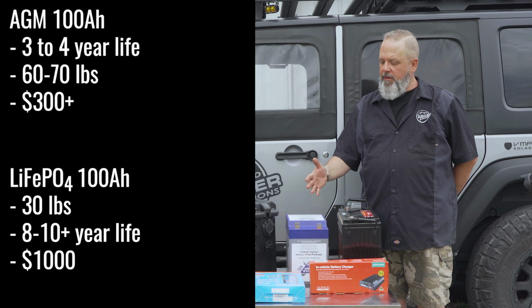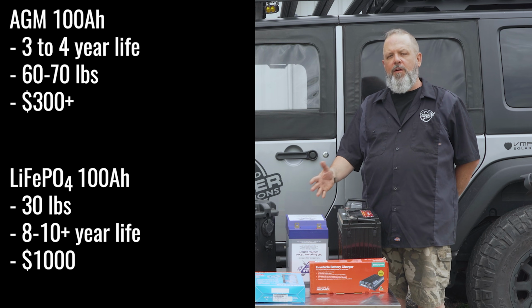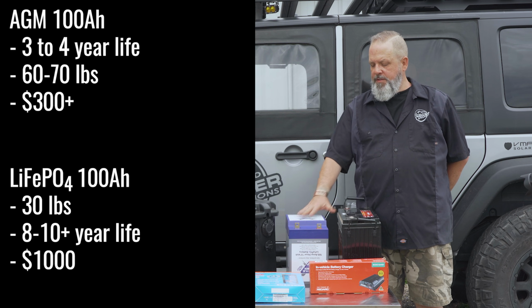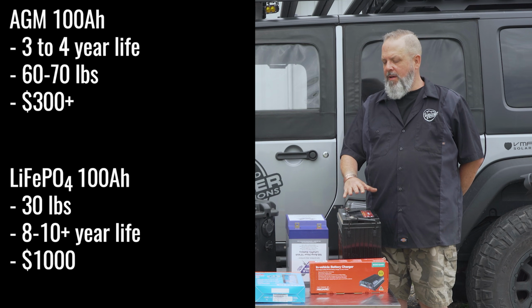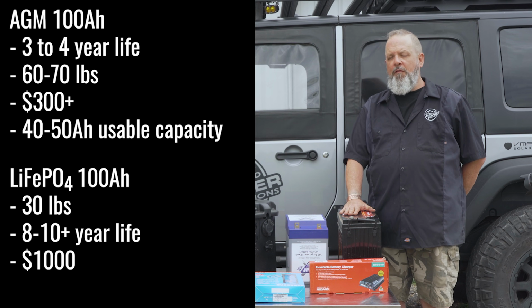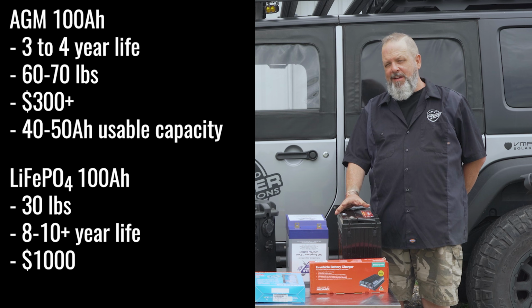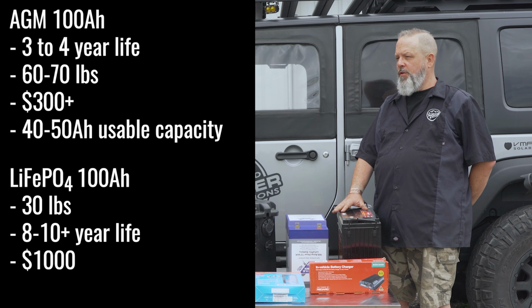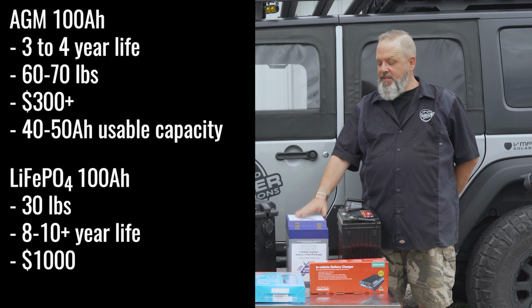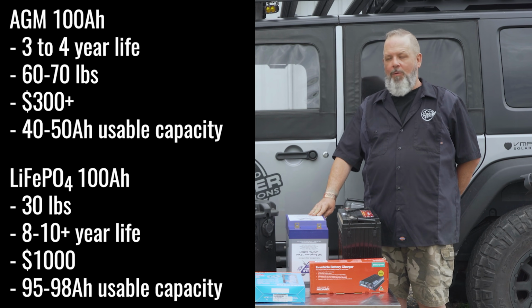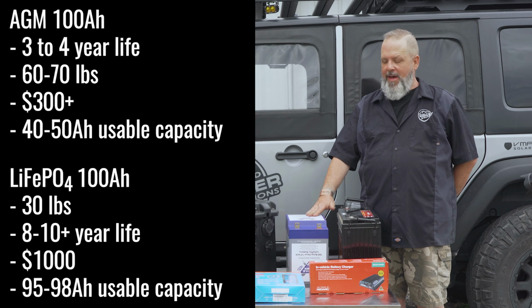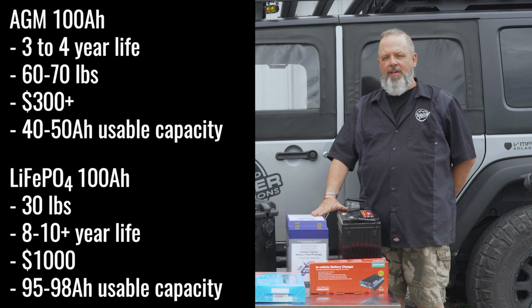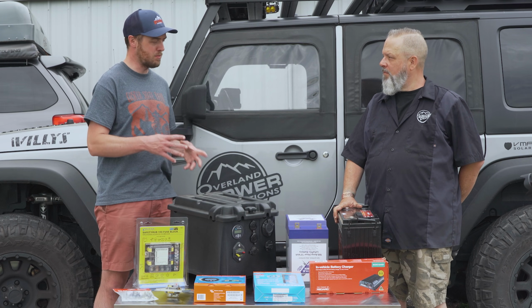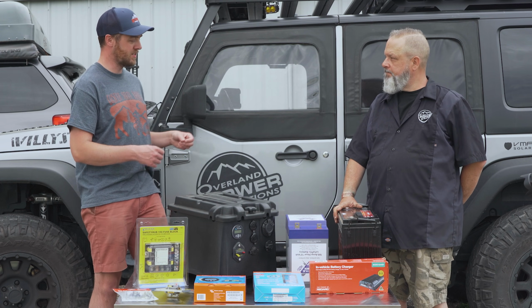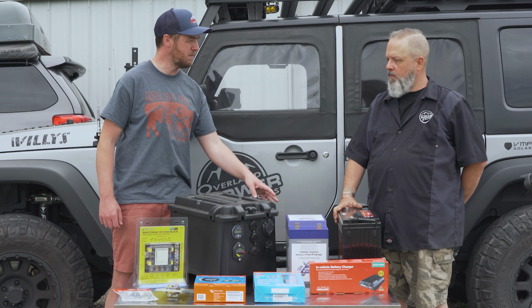The huge thing that also allows you to do is increase capacity. If I'm looking at these two batteries and I want to take my family off grid and have the things we need, the AGM gives me about 42 amp hours of usable capacity if fully charged, which you'll only get with a DC to DC system. The lithium battery gives me 96 or so amp hours. So you get 2 or 3 times the capacity, half the weight, and 2 or 3 times the lifespan. Even though they're about the same size and rated the same amp hours, the usable capacity in the lithium one is way more, about double.